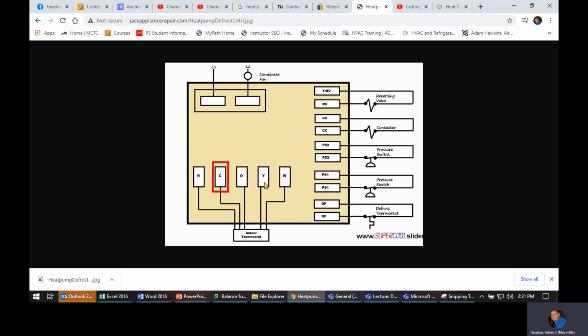The next one is yellow. A lot of people mistakenly think that yellow is cooling. Yellow is cooling on an air conditioner, but in a heat pump, it's heating as well. It's your first stage of heat. We think that W is heat because that's the way it is on a furnace or a single stage. But on a heat pump, your first stage of heat is Y. And Y energizes your compressor contactor. So regardless of if it's in heating or in cooling, if it's set up for heat pump, that thermostat is going to send a signal to Y. And it's going to say, okay, we need to run the compressor. And then orange is going to tell you what direction it sends the refrigerant.